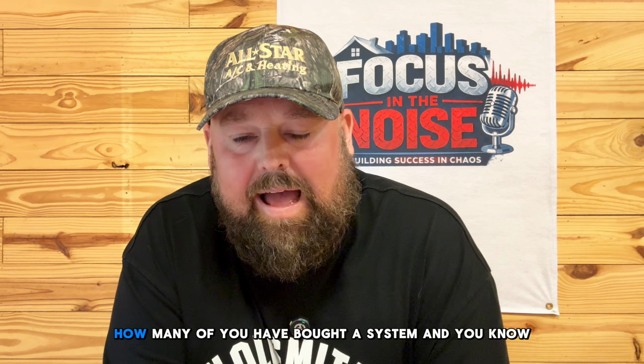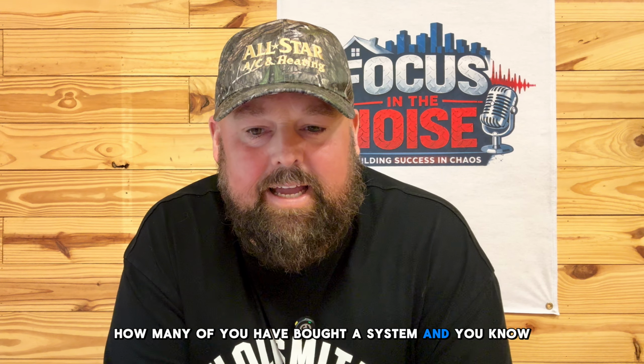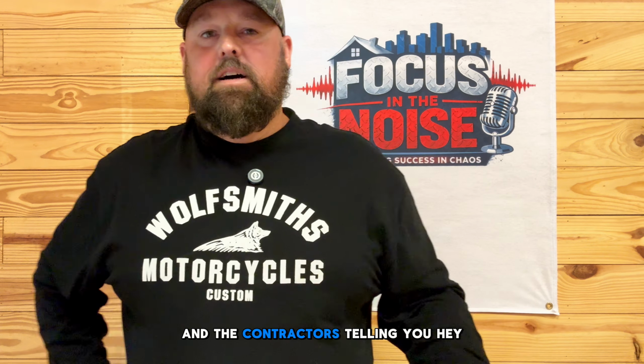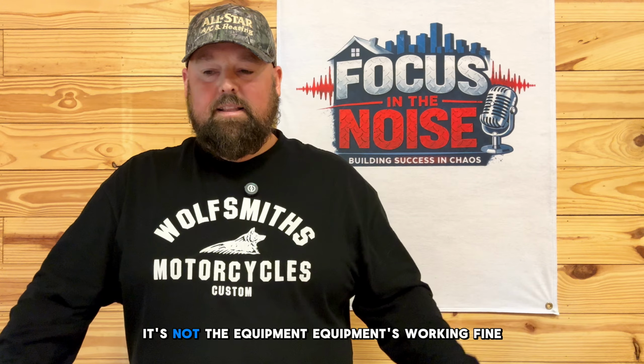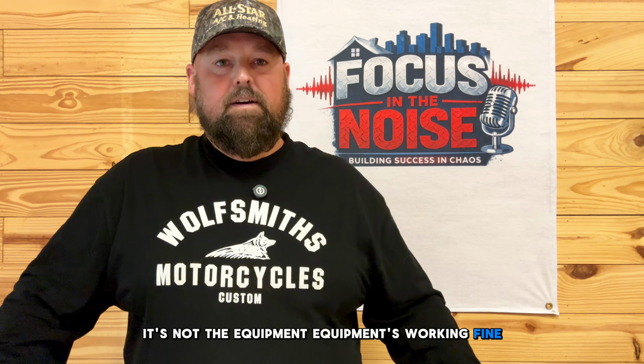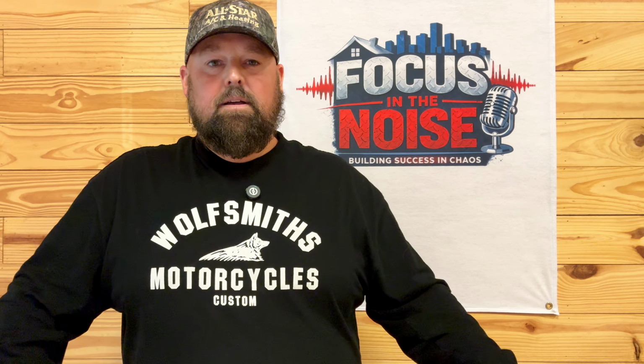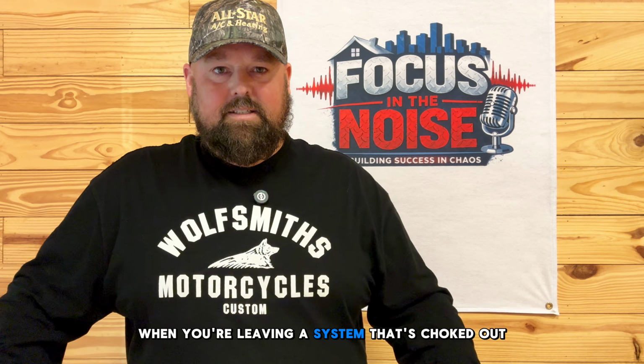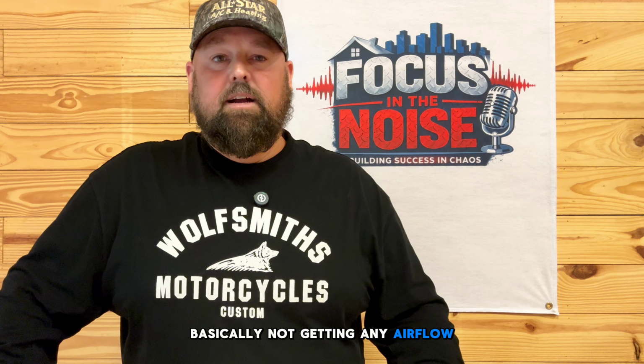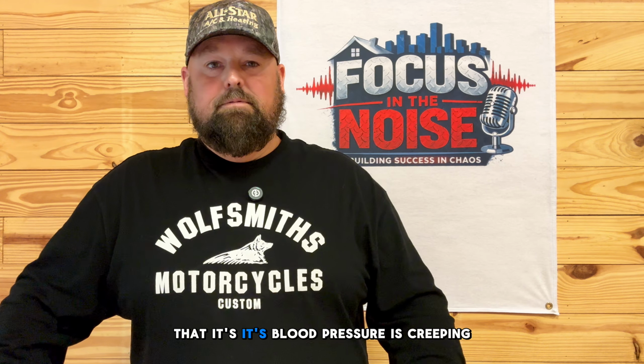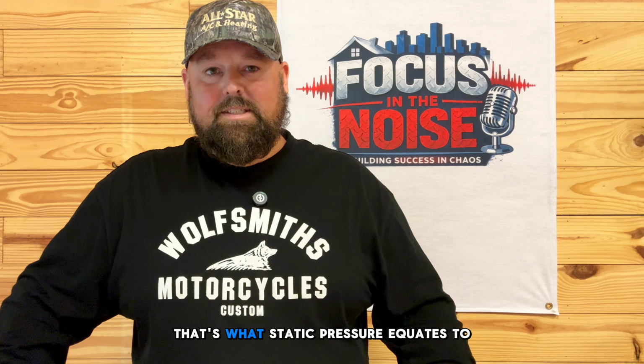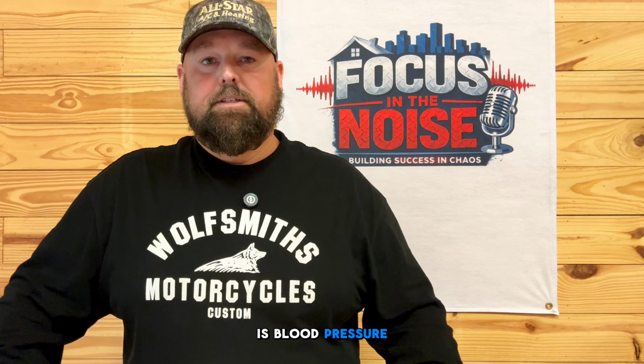So yeah, the supporting actors. How many of you have bought a system, got it installed, and it's still humid in the house? You've paid thousands of dollars and the contractor's telling you, hey, it's not the equipment, the equipment's working fine, I'm over here testing it. But did you know that when you're running a system that's choked out, basically not getting any airflow, its blood pressure is creeping? That's what static pressure equates to—blood pressure.